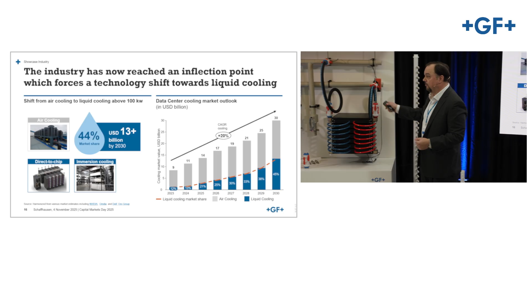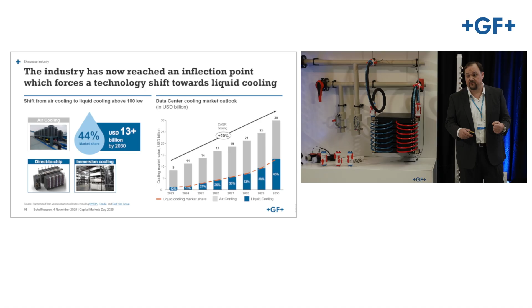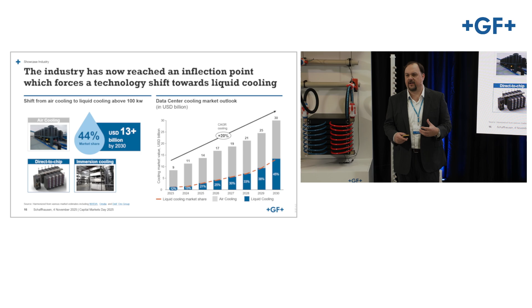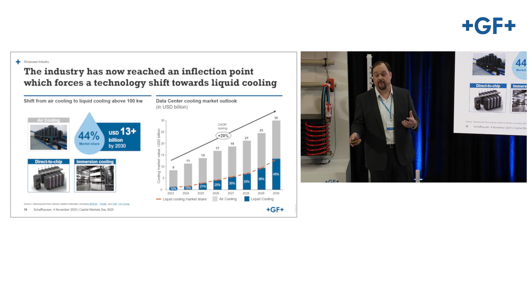However, there will always be a component of air, and devices that won't be air cooled. That said, the tectonic shift in this industry has been to liquid cooling. There are two main flavors, with sub-variants therein: direct-to-chip, often called DLC, direct liquid cooling, which is our big focus because it plays to our strengths and our history, specifically in microelectronics, but also labs, validated pharma, and so on. There's also immersion cooling, which we don't touch on as much at scale—it's a great way to transfer heat, but at scale it doesn't work as well for hyperscale neocloud operators, for reasons ranging from floor loading to EH&S concerns.